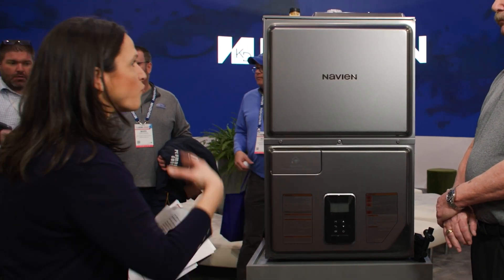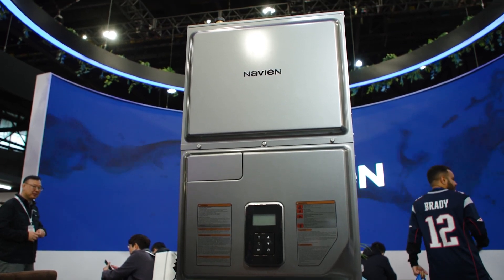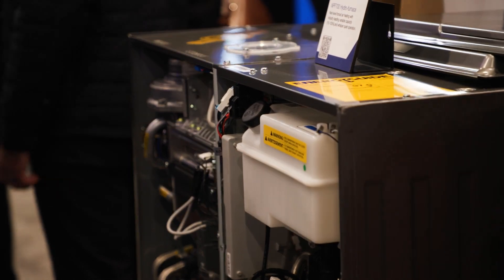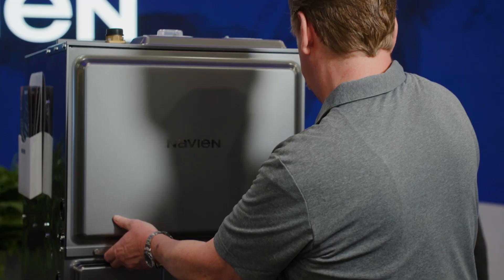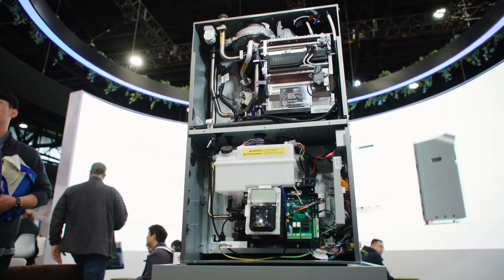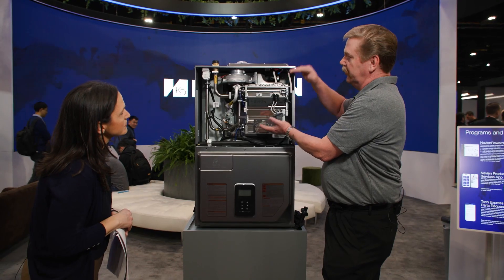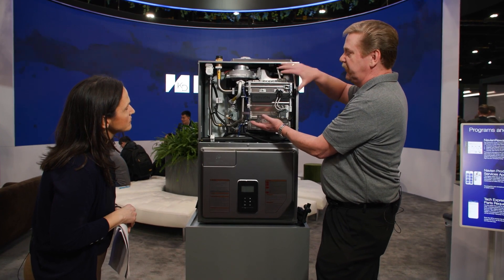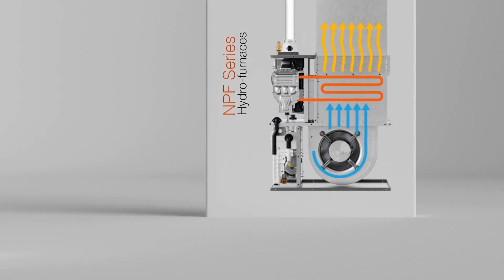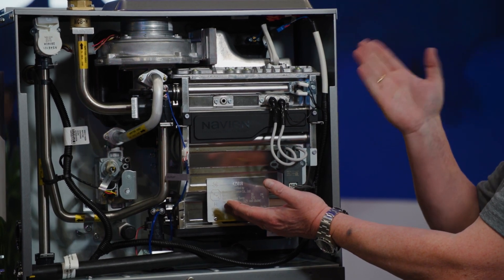Could you describe what is so unique about the hydro furnace? What's unique is that we're not firing the gas in the heat exchanger as the industry has done for a hundred years. We're taking the burning of the gas out of the airflow entirely, which makes the unit much more quiet. So normally in a normal furnace you'd see the heat exchanger in the airstream — we've taken it entirely out of the airstream. We're burning gas totally unique and out of the airstream, which makes the unit much quieter. This is one of the quietest units you can buy in the market today.